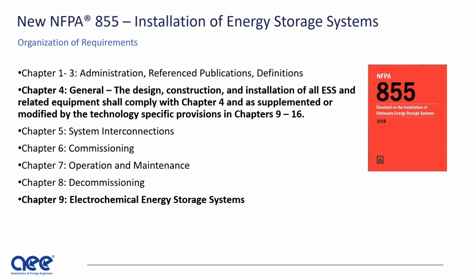I'm going backwards a bit here, but I wanted to lead you to this: making sure proper commissioning is done when the system is installed is really important too. You want everything checked, not just somebody coming in, dropping the connections, and walking away. You want to make sure your interconnections operate correctly—when it's supposed to come online, it comes online, and when it's supposed to go offline, it goes offline. And if you're using batteries, make sure the charging methodologies work.